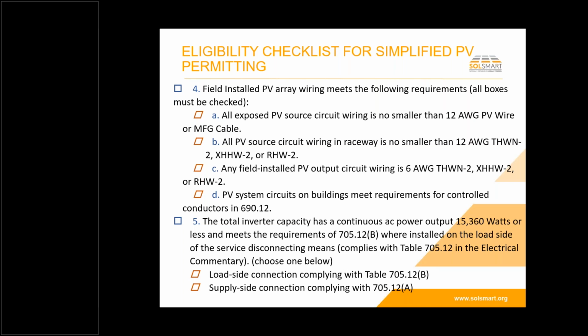Okay. Total inverter capacity is no more than 15.3 kilowatts, which is a very large system, but when we look at the requirements of 705.12 and how we interconnect things, it makes it easier if we limit the total amount of power. And there's other reasons why the total amount of power might be limited in a place like Virginia. Dominion Energy and the other Virginia utilities will probably have limits on the largest systems that you could interconnect through a simple interconnection agreement. And so those are also relevant, and we're not trying to go into all the details of every single utility's interconnection requirements. We're just saying from an electrical code point of view, if we limit it to no more than 15 kilowatts, it'll make our installations easier.